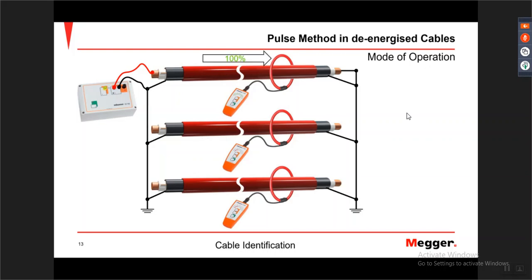100% of the signal will go through the core and through the coil. It separates at the end connections. 60% will go back through the coil on the cable connected to the generator, and 20% each will go back through the other 2 cores.